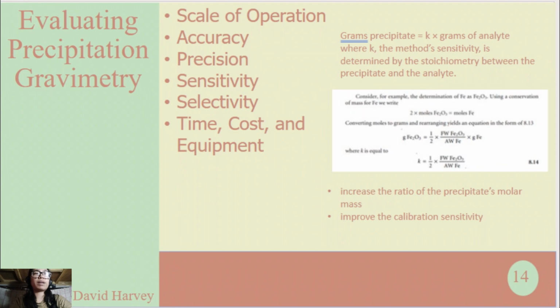Microanalytical balances are needed for trace level or microsamples. The accuracy of macro samples containing major analytes is typically 0.1 to 0.2%, with limitations due to solubility losses, precipitate impurities, and handling loss. Precision depends on sample size, with 1 to 2 ppt for smaller amounts and several ppm for larger amounts, a level rarely achieved by other quantitative techniques.